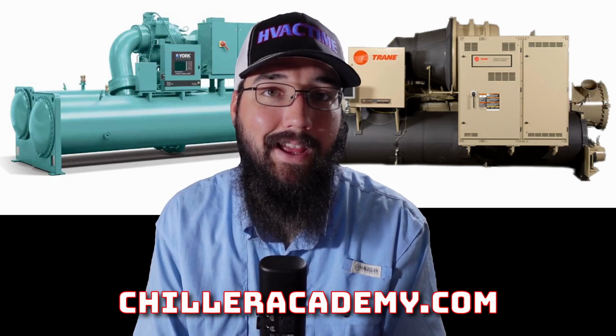Where with our low pressure refrigerants, we're getting into one of the older ones, which is R11, which operates at a negative 6.8 PSIG. Yes, negative, so it's in a vacuum. 123, which was a negative 8.2 PSIG, this is at 45 degrees of saturation on the evaporator.